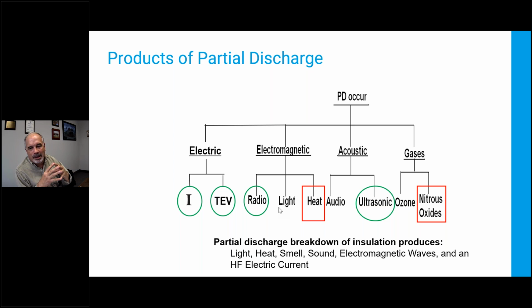And don't get too excited about, oh, it's heat, I can pick it up with an infrared gun. It's plasma, but it's plasma that exists for a microsecond out of every half cycle. So a microsecond out of 8,000 microseconds, or 8 milliseconds, is a pretty low percentage. So it averages out the heat, and an infrared gun is usually not going to find PD unless it's really in the catastrophic, about to fail, time to run sort of zone. So an IR gun is not a good detector of partial discharge.